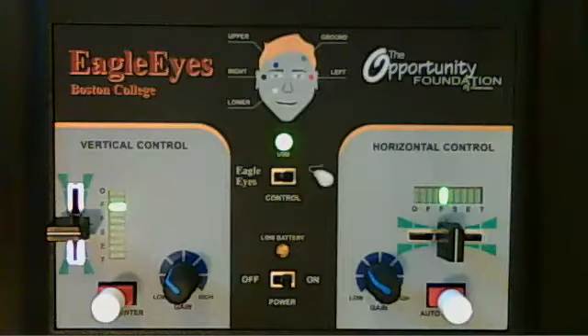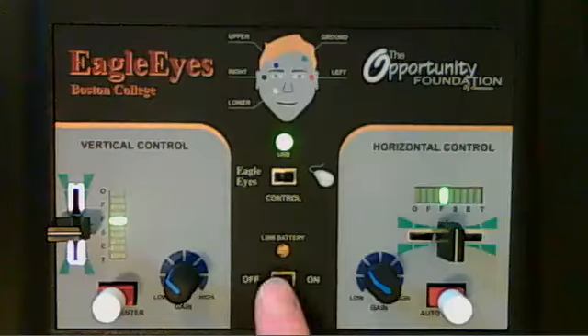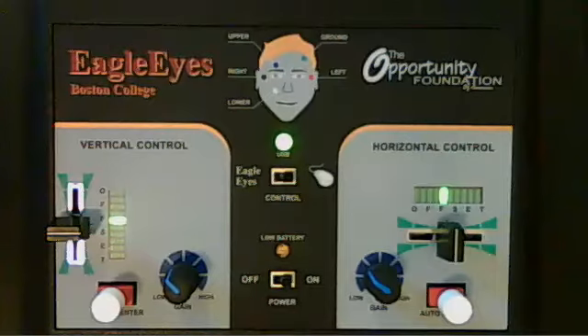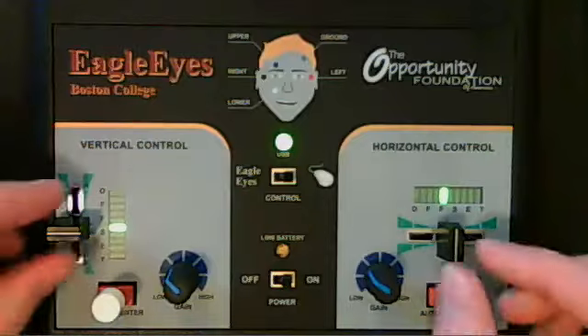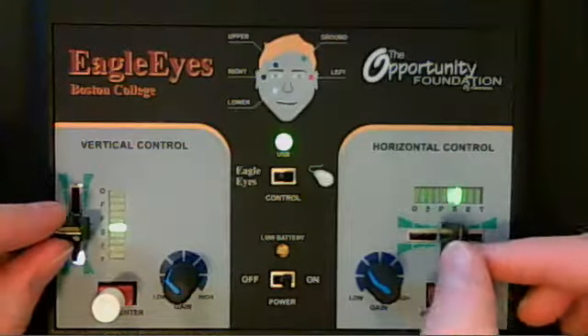Now, we actually already showed you this during our demonstration, but we just want to review it. Whenever you start using the console, you want to do a pre-calibration before you connect the user. Before you go to the effort and time of connecting all the electrodes, let's make sure that the system is working, that we have fresh batteries, that the computer is working, everything's working together. So to do that, we're going to turn on the system, plug in the USB to the computer, and then launch the software.